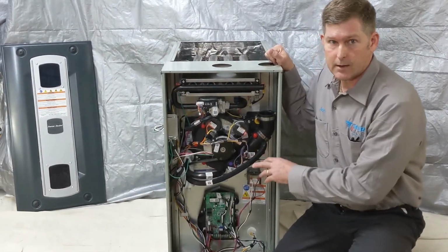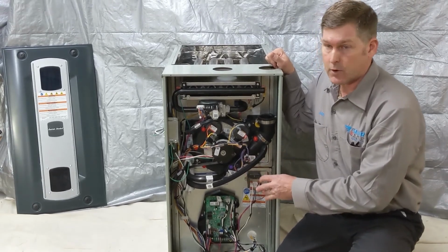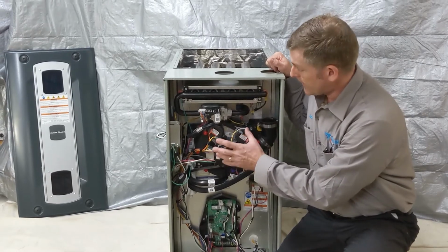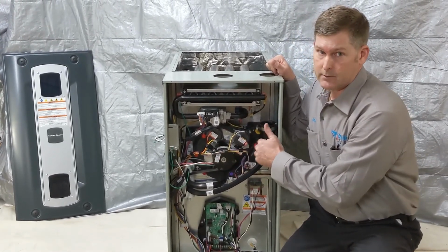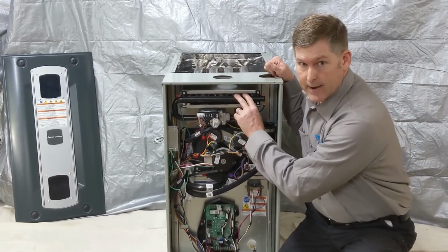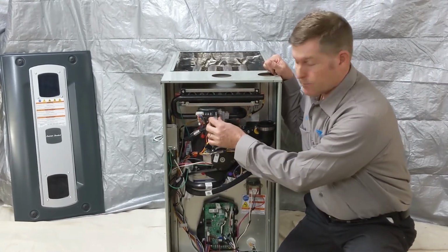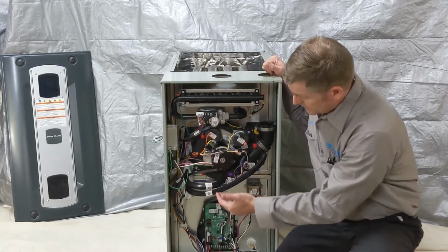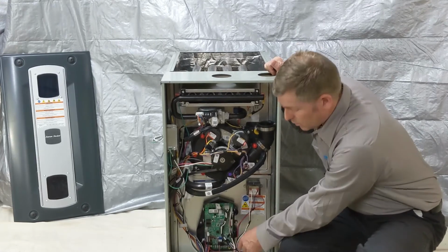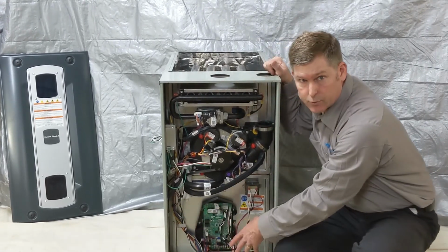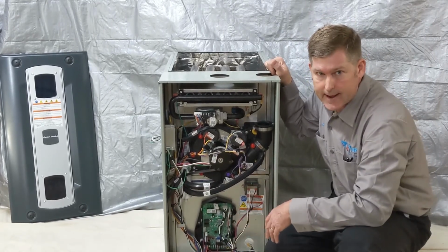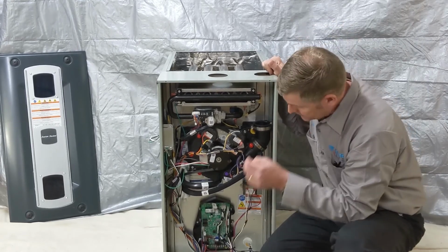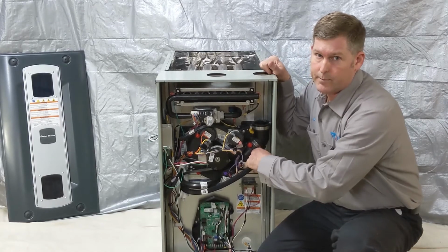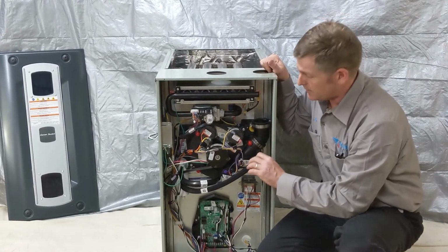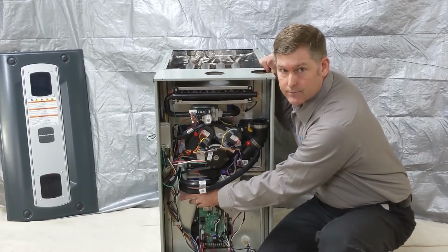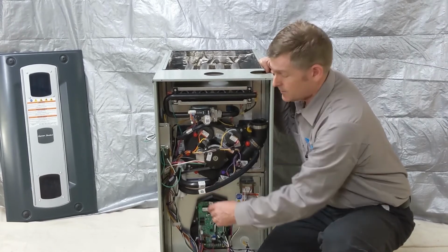As we move inside the furnace, American Standard has really simplified the layout of this furnace. In the upper part of the cabinet, we've got the inducer motor assembly. That's what exhausts all the flue gas up and out the PVC vent pipe to the outdoors. We've got the burner manifold with the in-shot burners, the gas valve assembly right here, and some control wiring to go with it. In the lower part of the cabinet, we've got the control board and wiring harnesses down here with drip loops on the wires, so should any moisture collect inside the cabinet, it's going to drip off and stay away from those electronics. We also have very sturdy, well-built, heavy rubber drain tubes that are kink resistant. And we've got a condensate trap down here to funnel off all the condensate from the combustion process to be drained away from the furnace.